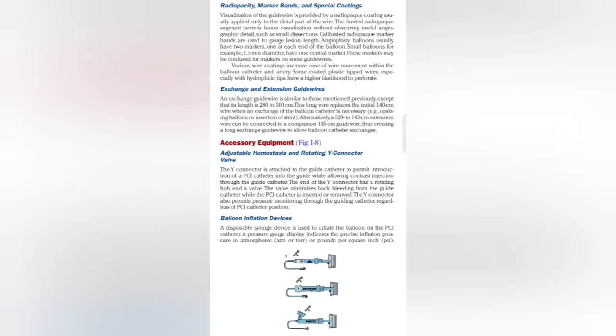Accessory equipment: adjustable hemostasis and rotating Y connector valve. The Y connector is attached to the guide catheter to permit introduction of a PCI catheter into the guide while allowing contrast injection through the guide catheter. The end of the Y connector has a rotating hub and a valve. The valve minimizes back bleeding from the guide catheter while the PCI catheter is inserted or removed. The Y connector also permits pressure monitoring through the guiding catheter regardless of the PCI catheter position.